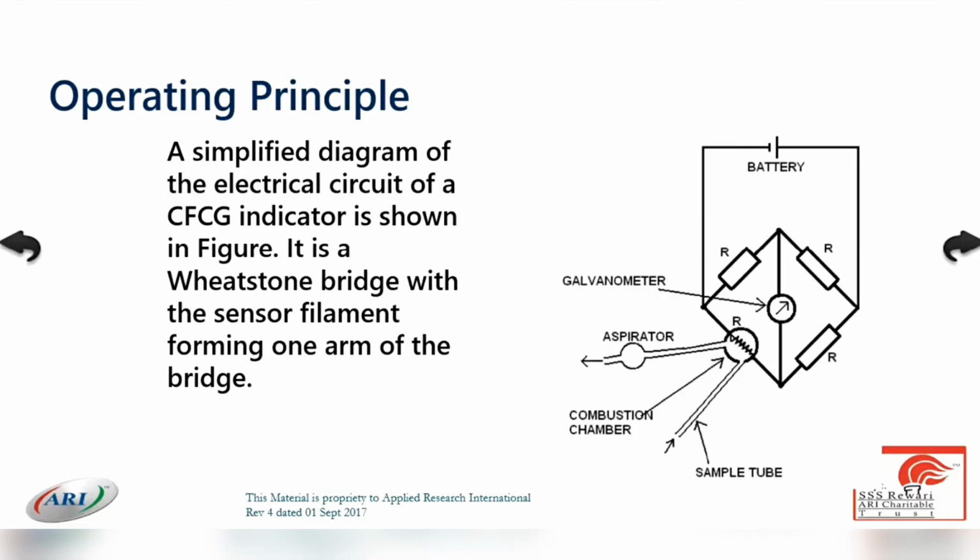There is a variation of resistance in both the cases. In the explosimeter, the resistance value is increasing because the temperature is increasing. In the tank scope, as the gas is absorbing heat, the filament temperature is falling, and the resistance value is decreasing. In both cases, the Wheatstone-bridge is getting imbalanced because there is a variation of resistance. Not all 4 resistors are the same. The amount of current flowing through the circuit corresponds to the hydrocarbon value by volume in the tank scope, and in LEL form in the explosimeter.